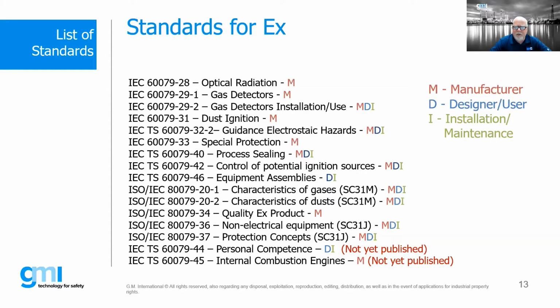And it's very much a similar document to your ISO 9001 certification. The other ones we'll talk about later are 36 and 37, which deal with non-electrical equipment and the protection concepts for non-electrical equipment. These are fairly new standards adopted by the IEC. Some other things on the horizon are 44 and 45, which deal with personal competency as well as internal combustion engines. Hopefully these two slides will tell you, as a manufacturer, designer, or installer, what the relevant standards are and where you should look for good information.